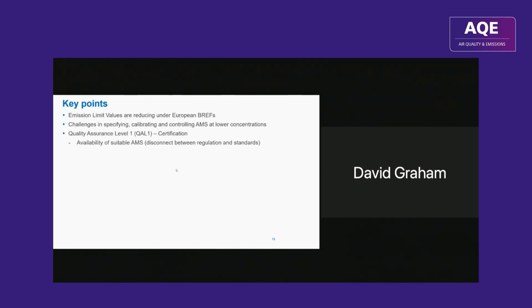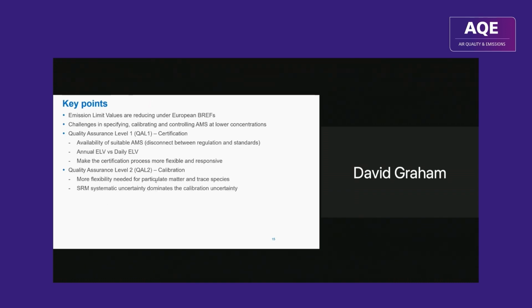So I'll just conclude with a brief wrap-up. ELVs are reducing under European BREFs. There are challenges in specifying, calibrating, and controlling AMS at these lower concentrations. In terms of type approval, there may not be a suitable AMS available. There's the question of using the annual rather than the daily for quality assurance assessment. The certification process needs to be more flexible and responsive. In terms of calibration, more flexibility is needed for particulate matter and trace species. The SRM uncertainty dominates the calibration uncertainty, and we've talked about the issues there and the importance of having a robust approach for compliance assessment.